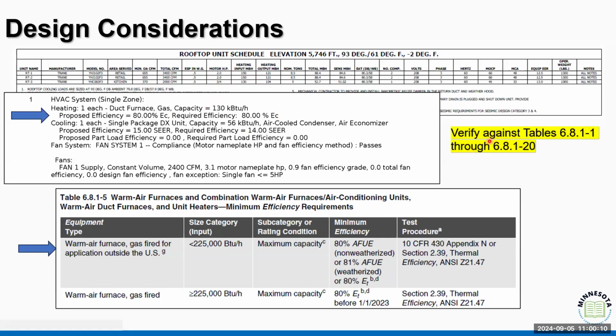And then we're going to compare that with our table, and we're going to find that this particular type of equipment, a warm air gas-fired furnace, comes under table 6.8.1-5. Based on the size, under 225 thousand BTU, this piece of equipment requires a minimum of 80% AFUE. And so we've got that 80% efficiency listed, so it matches - this would meet those minimum expectations.